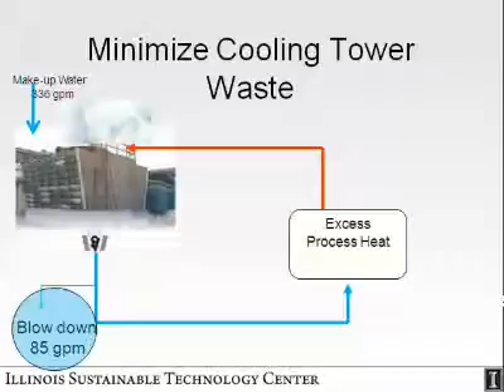So for example, let's go back to the previous slide. Okay, so do you see this? This is called makeup water, right? This is the amount of water that is coming into the cooling tower. And I told you 545 gallon per minute is what we're taking in as a total. And then 336 GPM of that is going into the cooling tower. Most of this 336, about 248 gallon per minute, is actually evaporated, and this is the rest of it. More than 50%? Oh yeah, it's usually the evaporation about 85% of the total makeup. Typically, that's what you would use for design purposes.